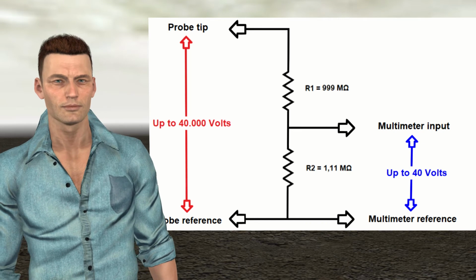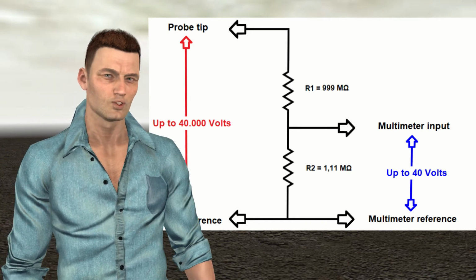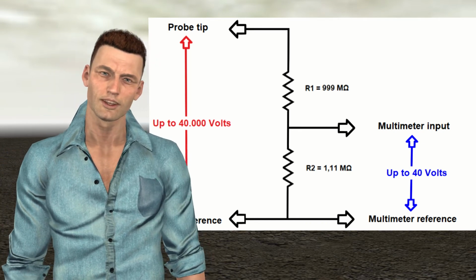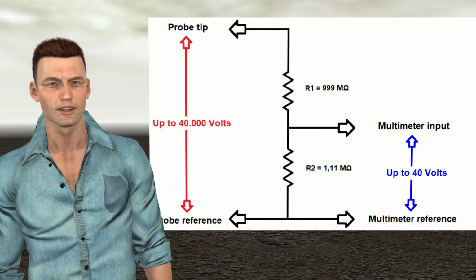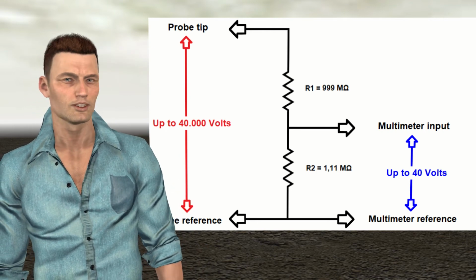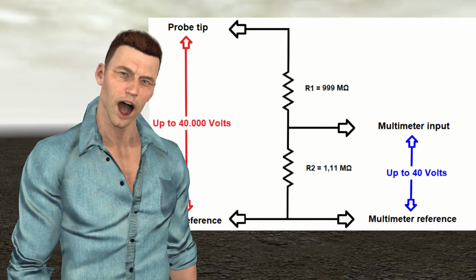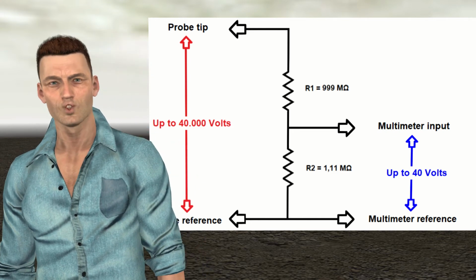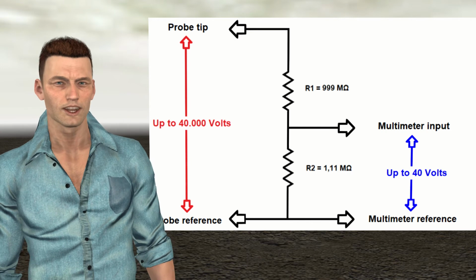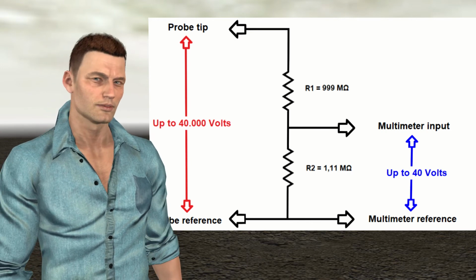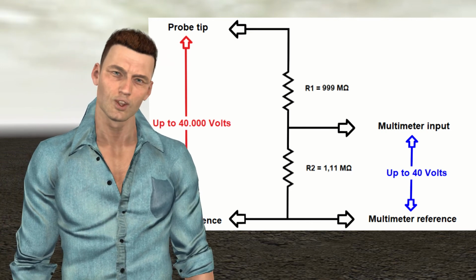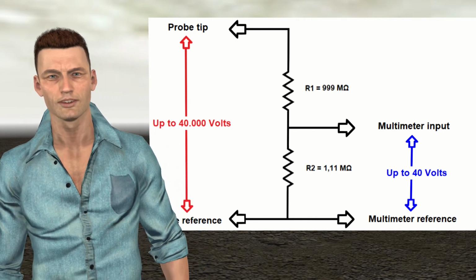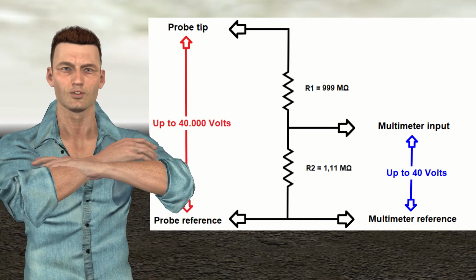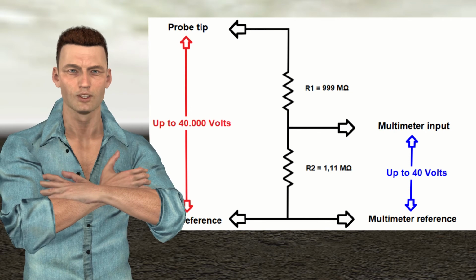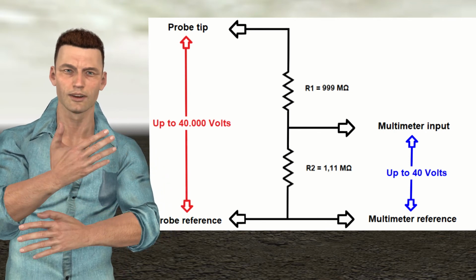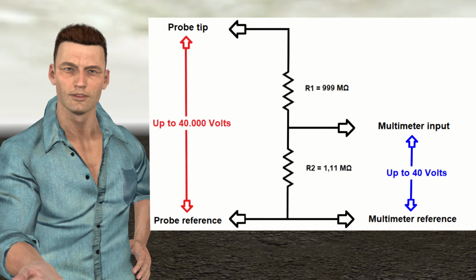As we can see, the resistance R2 would be in parallel with the input impedance of the multimeter, so that the equivalent resistance that we obtain between R2 and the 10 mega-ohms of the input impedance of the multimeter gives us a value of 1 mega-ohm. In this way, the total impedance of the probe will be 1000 mega-ohms, and when applied to a 40,000 volt circuit, it will take a current of 40 microamps, which will lead to a voltage drop of 40 volts at the input of the multimeter. In this way we confirm the indicated transformation ratio of 40,000 input volts and 40 output volts.